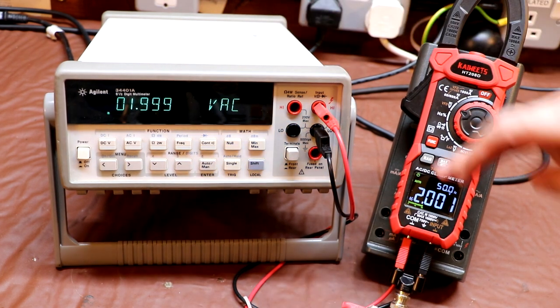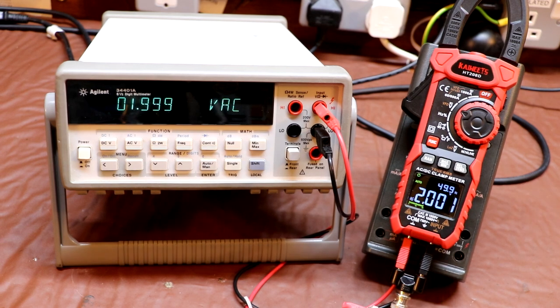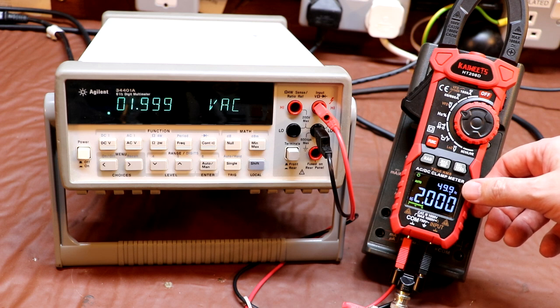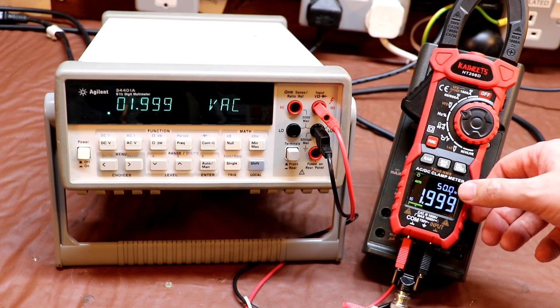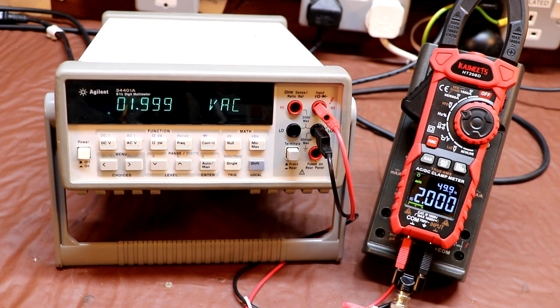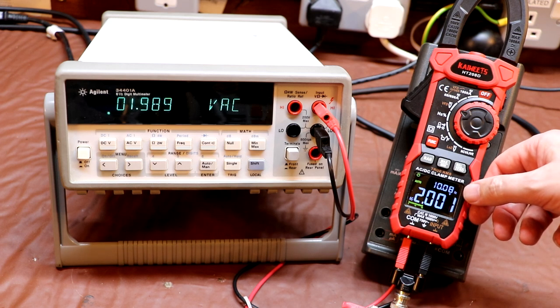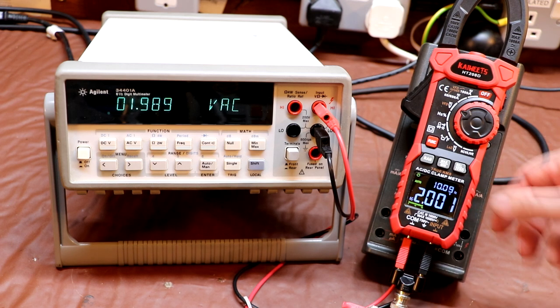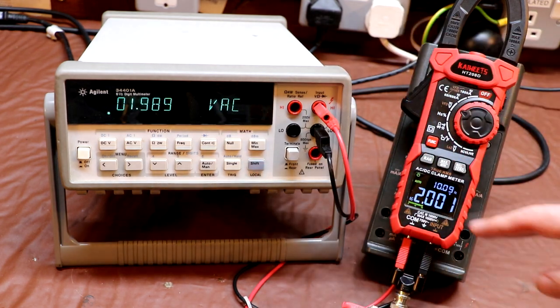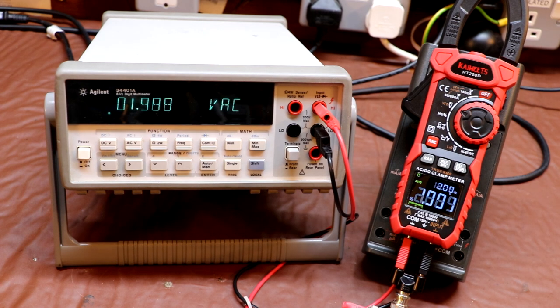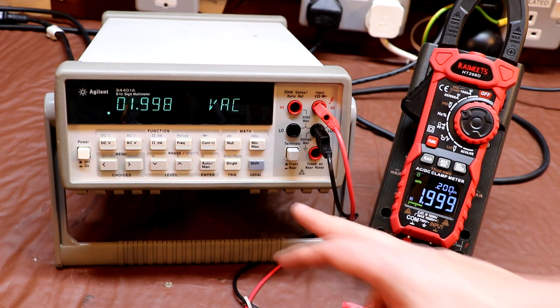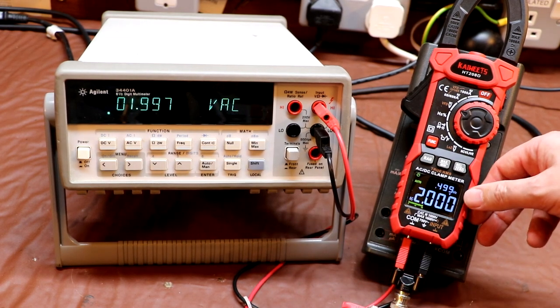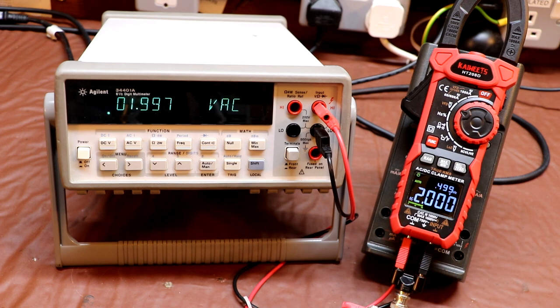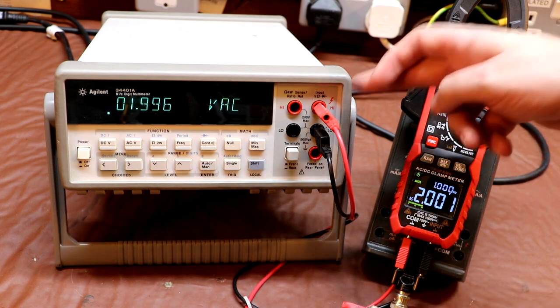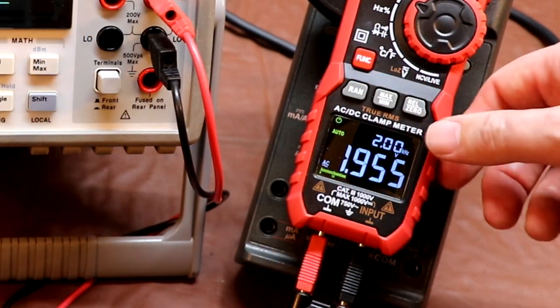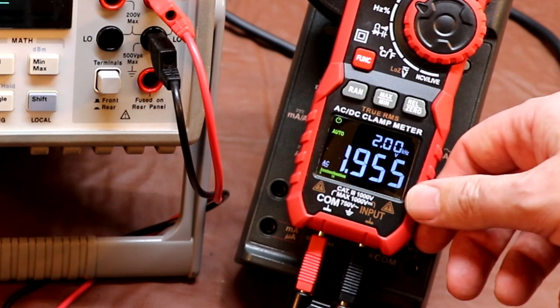Now at 50 Hz both of our meters are reading within a count of each other, so that's pretty good. On the AC voltage range, the KAIWEETS meter will also indicate the frequency, and it's flicking between 49.9 and 50 Hz. Let's drop the frequency now to 10 Hz. The frequency indication on the KAIWEETS meter is now showing 10 Hz, and the voltage difference between the Agilent meter here and the KAIWEETS is just out by a couple of counts. The frequency now shows 200 Hz and the meters are within 1 count. 500 Hz is indicated on the KAIWEETS and the meters are within 2 counts. 999 Hz is indicated and the meters are within 5 counts. 2000 Hz is indicated on the KAIWEETS and it's within 2 counts.